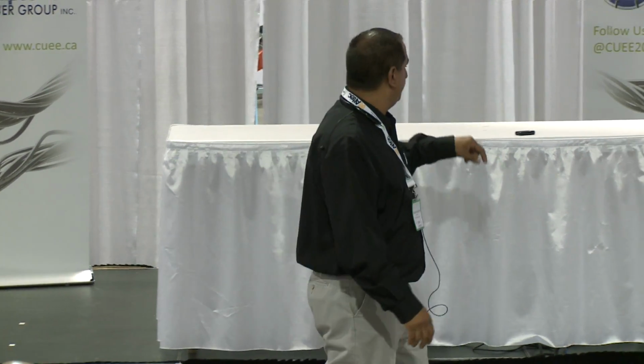Now, where we would supply something like this would be to your first response teams. You have an outage in the middle of the night, you've got a loop system. I've got 8 transformers in my loop. I don't know which section of cable is bad. To cut down on the amount of time going from transformer to transformer all the way down, you hook up, you send that pulse down, you apply voltage to it, and it tells you where my fault is. It's between my second and third, my fourth and my fifth, wherever that fault is. So what you do at that point to sectionalize, I'm not worried about finding a fault at 2 o'clock in the morning. I'm worried about getting the power back on. So what you can do is determine which section is bad, shows you where the fault is, backfeed it, get everybody back on, and then you can locate it tomorrow.